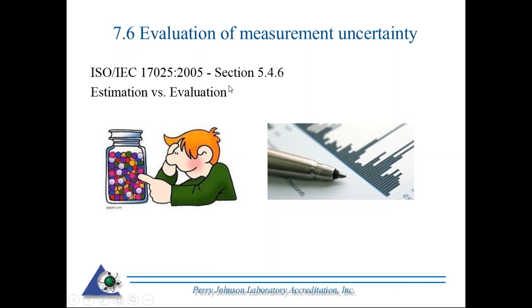Now the laboratory shall identify the contributors to measurement uncertainty. All laboratories performing calibration, including of their own equipment, shall evaluate the measurement uncertainty. This is primarily, again, due to the electronic age. This is done more these days with computer software, having the user go through and identify contributors and quantify them through a spreadsheet rather than, say, a documented procedure. However, again, I know I'm repeating myself: if you're a calibration lab and you have uncertainty requirements specified, and you have a procedure, that procedure can still be used as a source to identify the contributors. However, a formal documented procedure is no longer required.